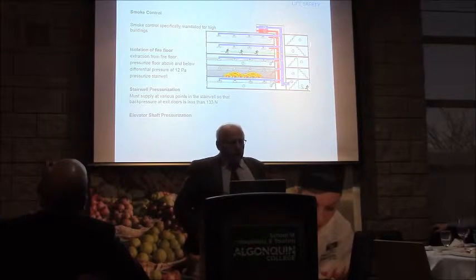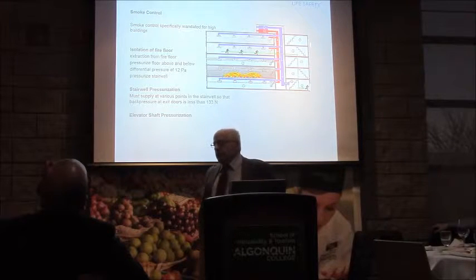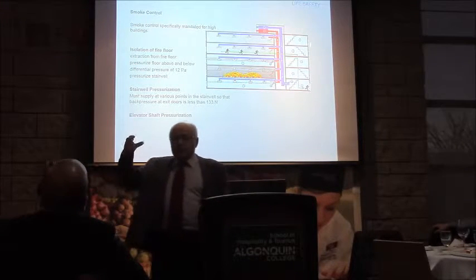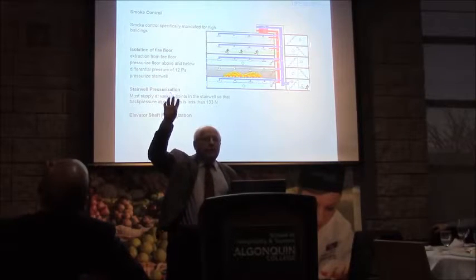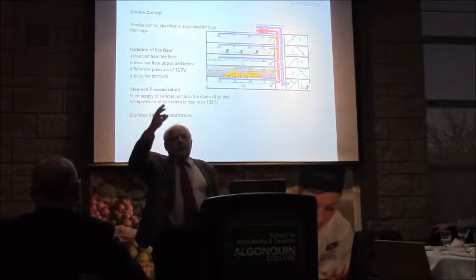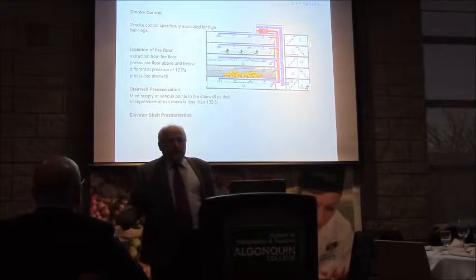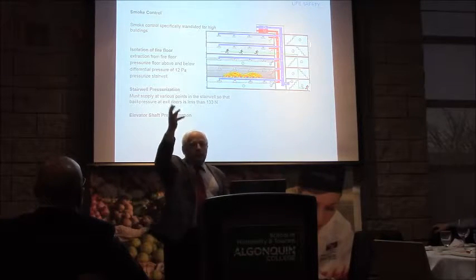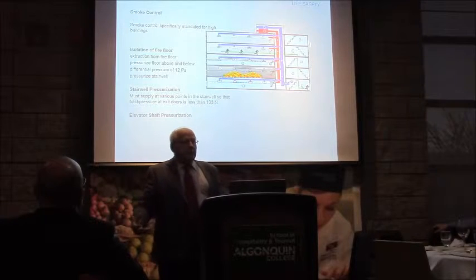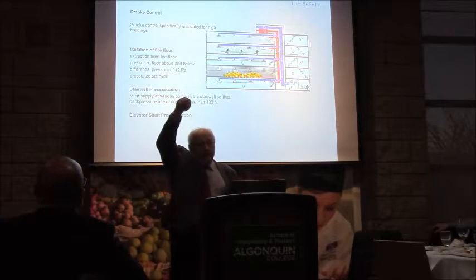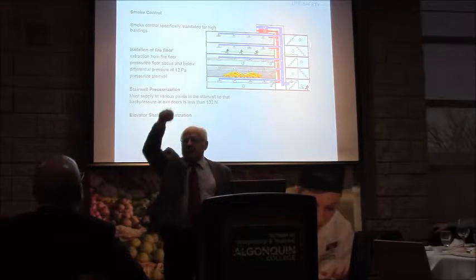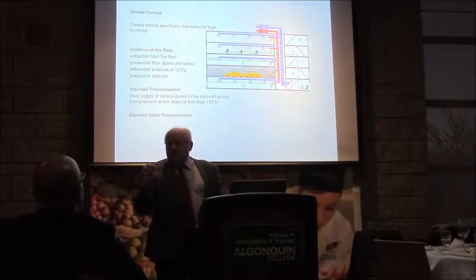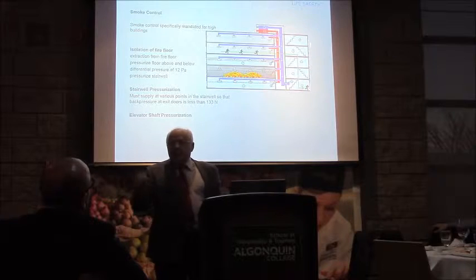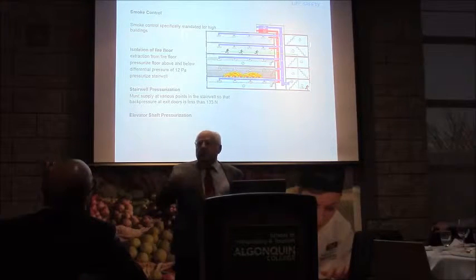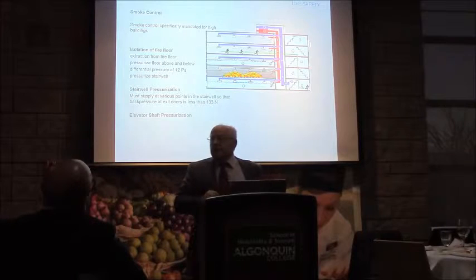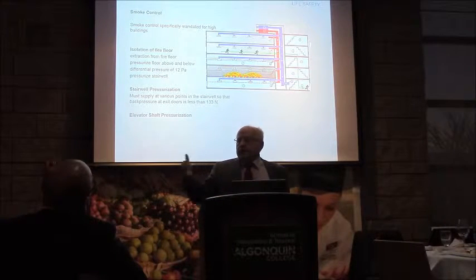So 133 newtons is the limit. The big thing is in a building, you cannot just supply air at the top and expect that the entire stair shaft is going to be pressurized equally. You've got pressure losses, just like you would have in a duct. So you need a separate distribution system going vertically and tying into the stair every 6 or 7 floors, supplying air into it at an even pressure so you can regulate that door pressure.